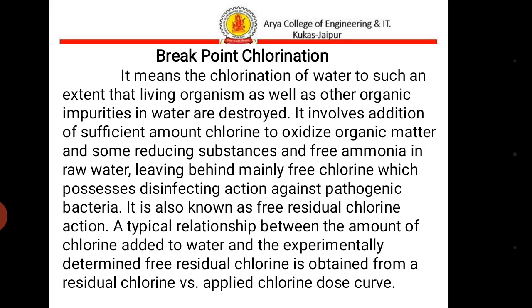Now we will start breakpoint chlorination. It means the chlorination of water to such an extent that living organisms as well as other organic impurities in water are destroyed. It involves addition of sufficient chlorine to oxidize organic matter, some reducing substances and free ammonia in raw water, leaving behind mainly free chlorine which possesses disinfecting action against pathogenic bacteria.